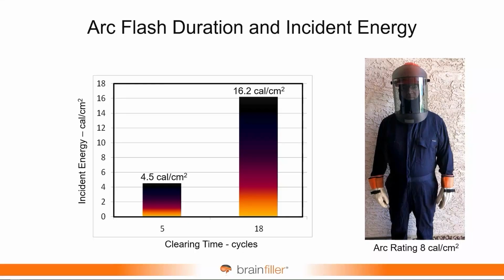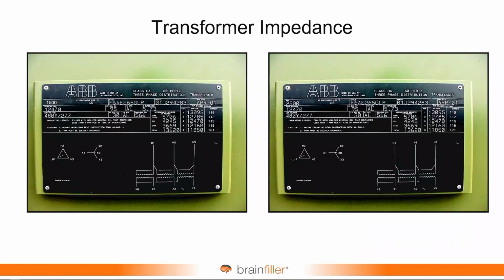Now, what we're really looking at, the concern is if the incident energy changes enough where the PPE that was specified is no longer adequate. So if there's a change where this goes from 4.5 to, let's say, 16.2 calories per square centimeter, that would be a problem because the 8-calorie PPE would no longer be considered sufficient. What can cause changes like this? Well, the reference to transformers.